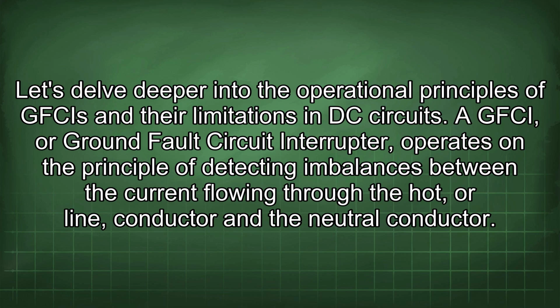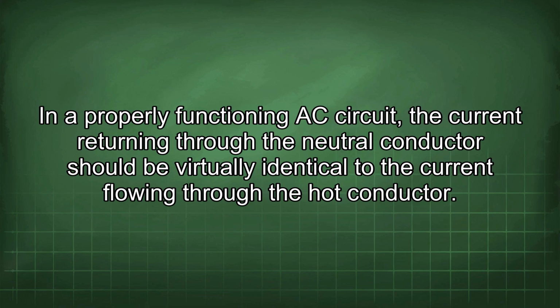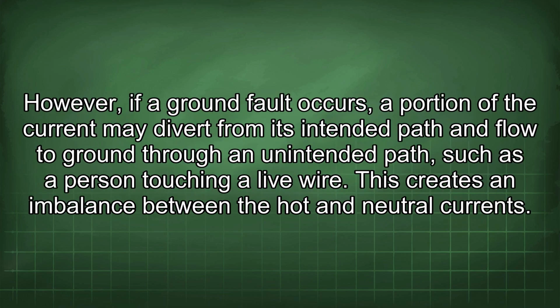A GFCI, or ground fault circuit interrupter, operates on the principle of detecting imbalances between the current flowing through the hot, or line, conductor and the neutral conductor. In a properly functioning AC circuit, the current returning through the neutral conductor should be virtually identical to the current flowing through the hot conductor. However, if a ground fault occurs, a portion of the current may divert from its intended path and flow to ground through an unintended path, such as a person touching a live wire. This creates an imbalance between the hot and neutral currents.